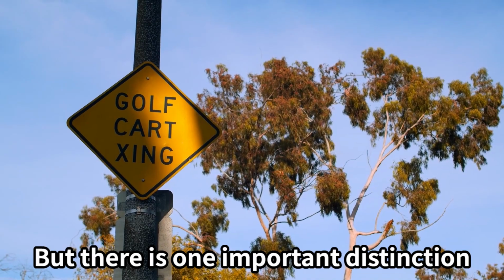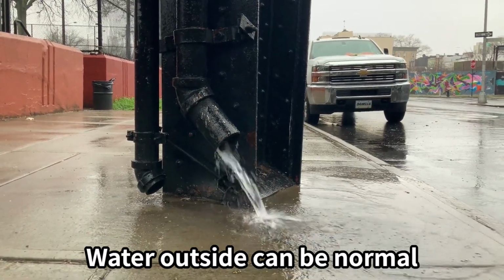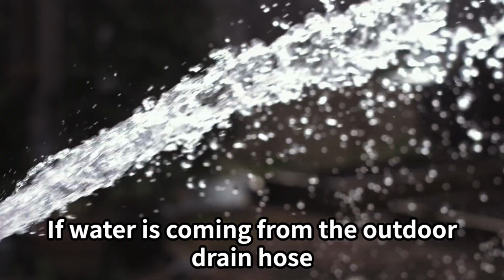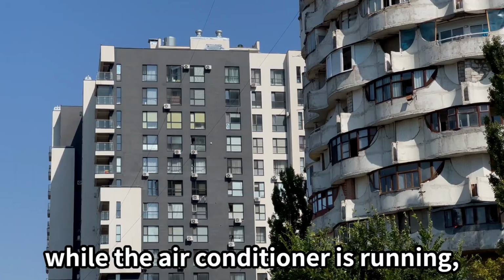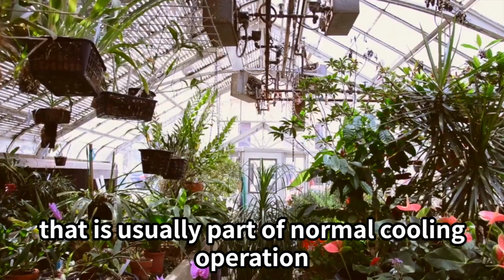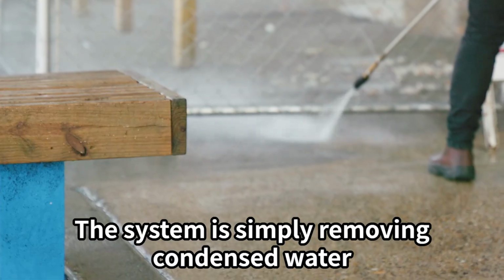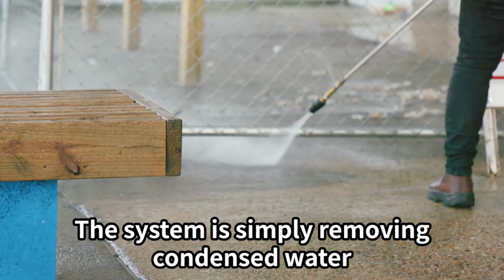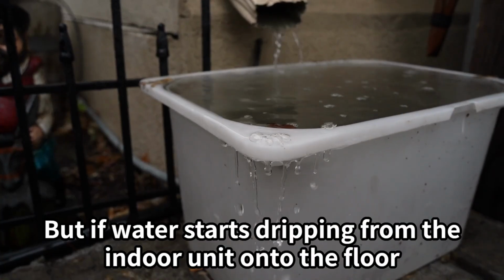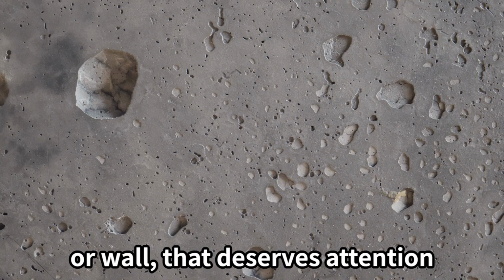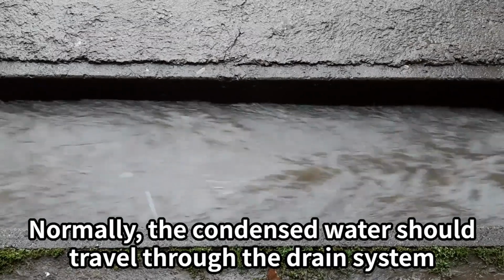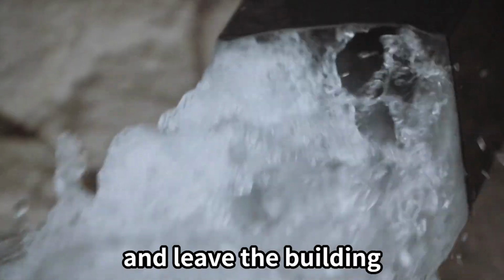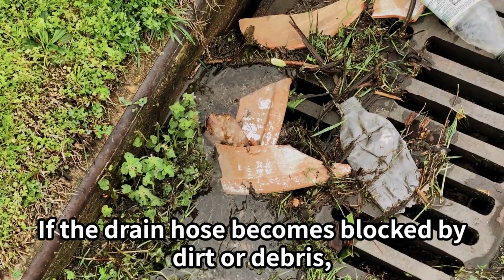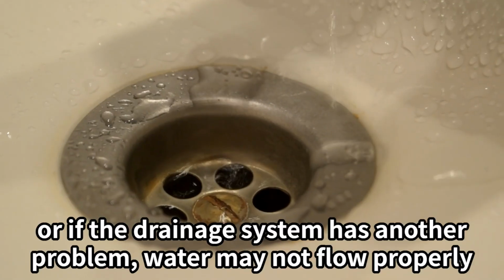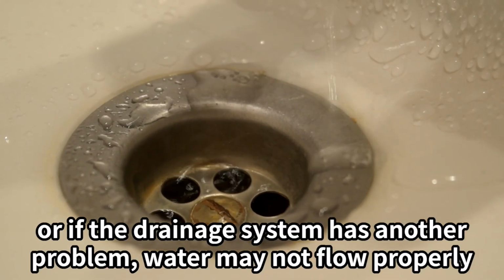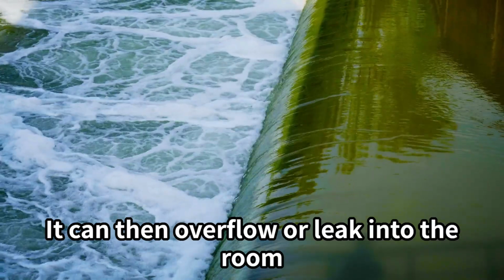But there is one important distinction. Water outside can be normal. Water inside may not be. If water is coming from the outdoor drain hose while the air conditioner is running, that is usually part of normal cooling operation. The system is simply removing condensed water. But if water starts dripping from the indoor unit onto the floor or wall, that deserves attention. Normally the condensed water should travel through the drain system and leave the building. If the drain hose becomes blocked by dirt or debris, or if the drainage system has another problem, water may not flow properly. It can then overflow or leak into the room.